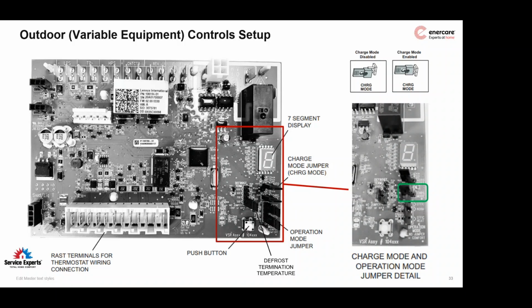Thanks, Terry. Thanks, Richard. Jim, may I also ask about this? It's Anthony. Sure. So for this outdoor variable unit, wouldn't it be required to have an S40? No, you can run with both. Oh, would it need the EIM, or you can just run 24V? You can run 24 volts. Totally. The only scenario where you would need an EIM is if you've got a non-communicating piece of equipment inside. Actually, no, I don't even know if you need that. Well, the only reason you would ever need an equipment interface module is if you're putting in a communicating piece of equipment or a heat pump outside, or a non-communicating heat pump with a communicating system.